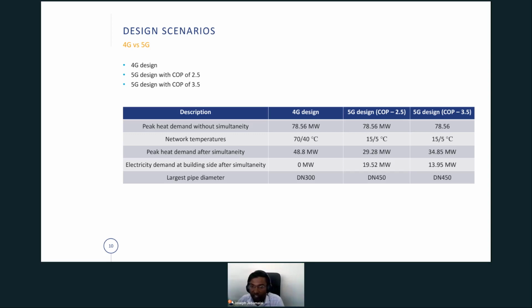So if we compare these 3 designs, we have a peak heat demand, without simultaneity, of about 78 megawatt. If we consider simultaneity, it turns out 48.8 megawatt is required for the 4th generation design. And then for the 5th generation, the thermal heat is 29.28 megawatt, and 19.52 megawatt of electricity is required for this particular case. And then for the case with the COP of 3.5, we require about 35 megawatt peak, and the electricity of about 14 megawatt. Of course, if you look at the pipe diameter, the largest pipe diameter is DN300 for the 4G design, but we have DN450 for the 5th generation design. That's because we have a very low temperature difference for the 5th generation systems when compared to the 4th generation design.